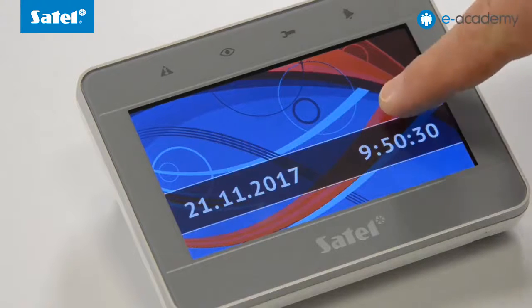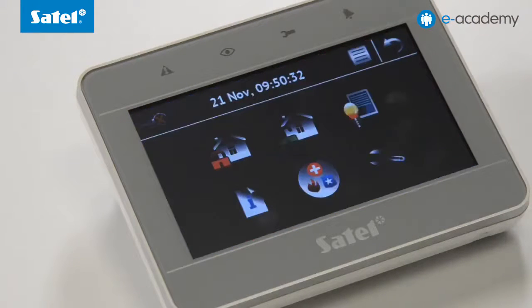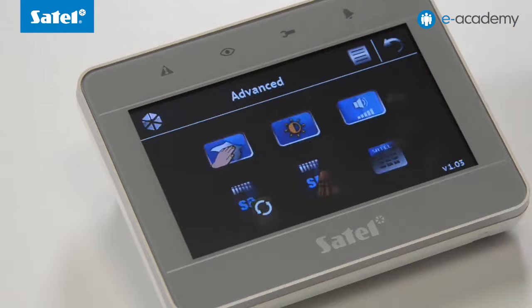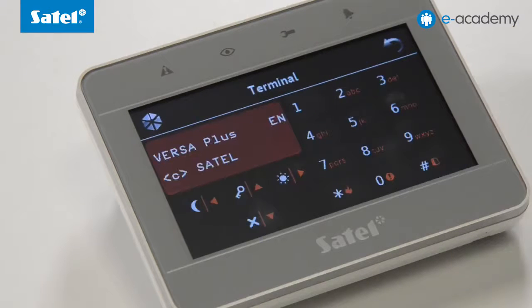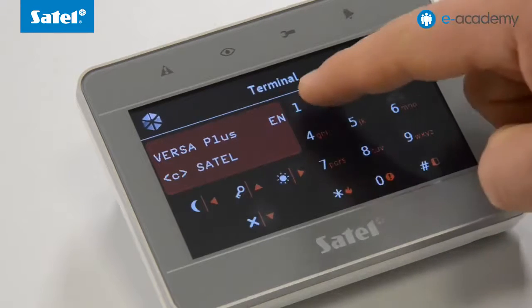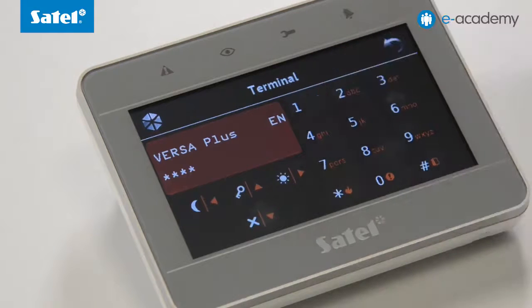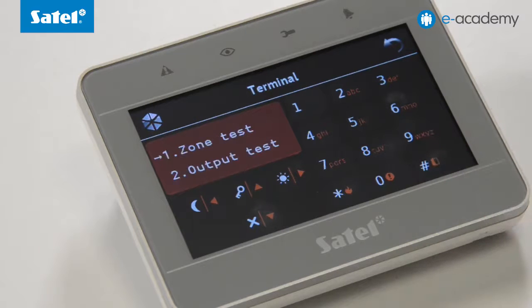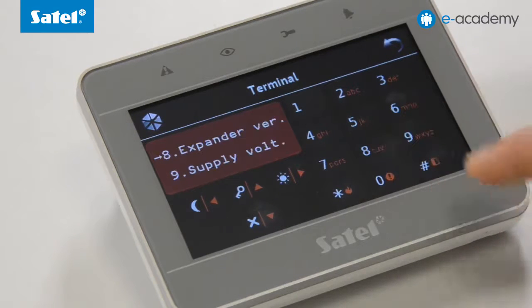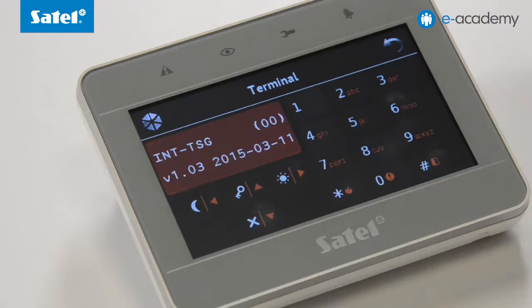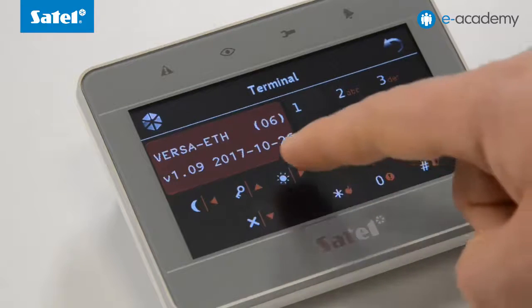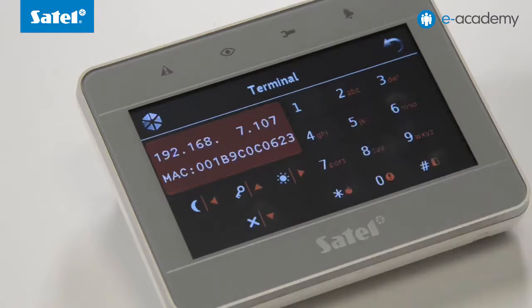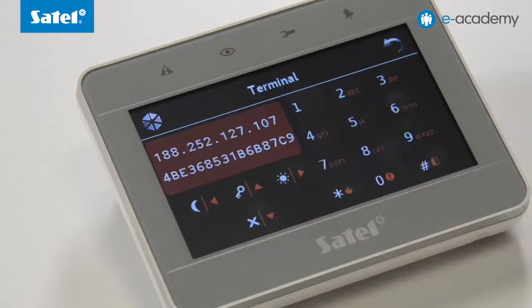To read the MAC address and ID from the keypad, go to the terminal from the keypad, then enter the user code 1111 and press star to enter the menu. Move to the tests item and then select module versions. Select the Versa ETH modules and use the left-right cursor to find the MAC and ID values.